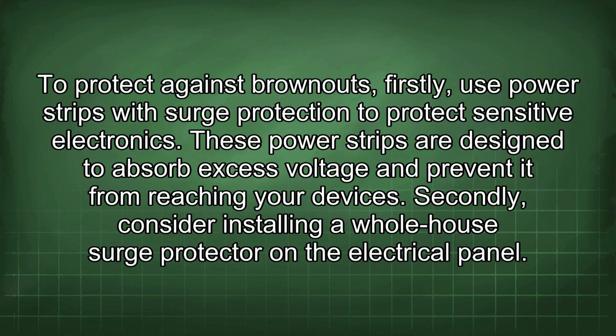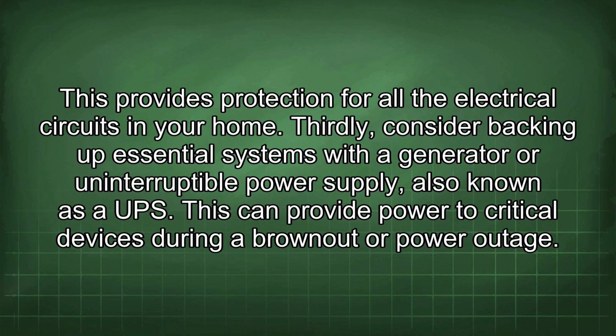To protect against brownouts, firstly, use power strips with surge protection to protect sensitive electronics. These power strips are designed to absorb excess voltage and prevent it from reaching your devices. Secondly, consider installing a whole house surge protector on the electrical panel. This provides protection for all the electrical circuits in your home. Thirdly, consider backing up essential systems with a generator or uninterruptible power supply, also known as a UPS. This can provide power to critical devices during a brownout or power outage.